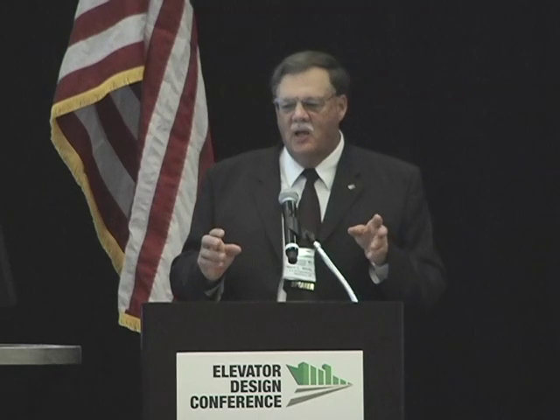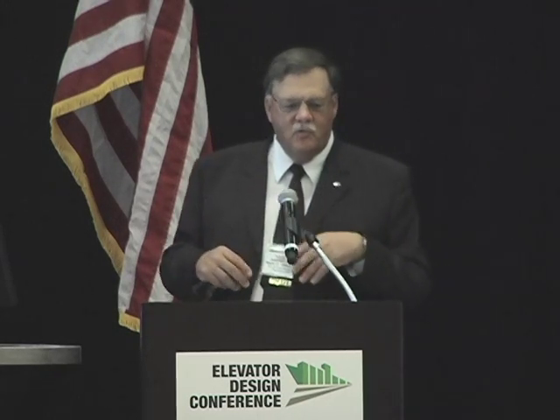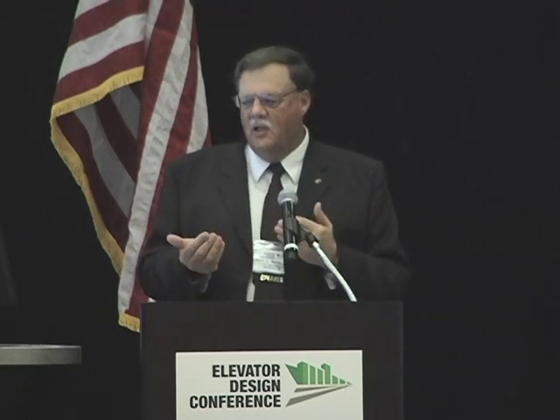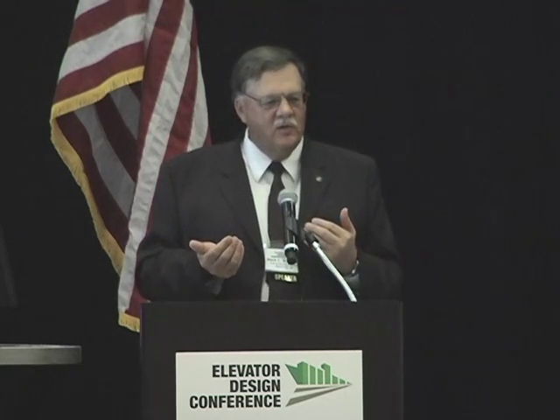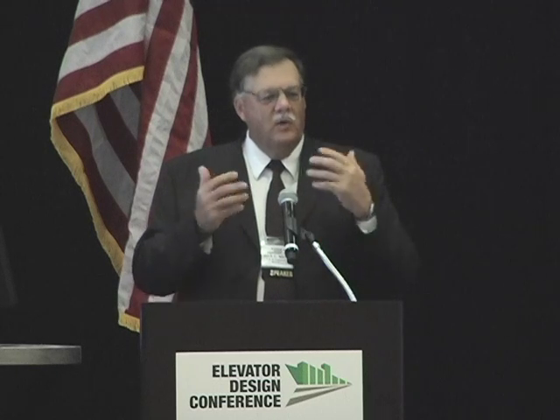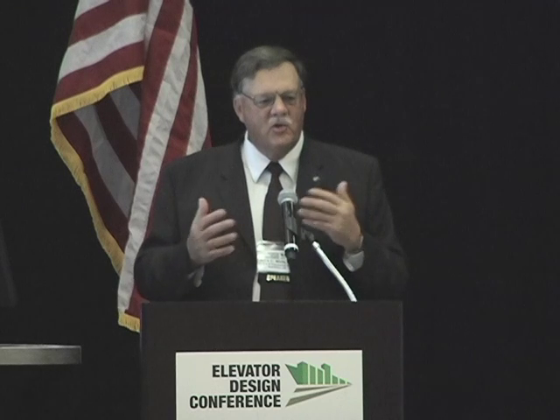We look at where there are opportunities on dust fans, where you may have a dust collection fan with multiple collection points and dampers on the system, where sometimes you're sharing collection with a truck receiving that's not always in operation with something else. And when you have variable conditions, you can get energy conservation by reducing the airflow, still meeting your CFM requirements as your collection system is being used in different modes of operation.